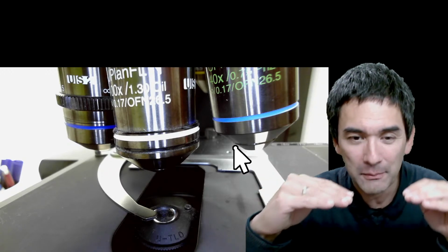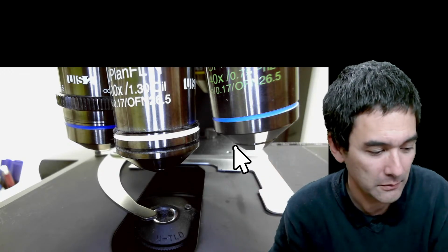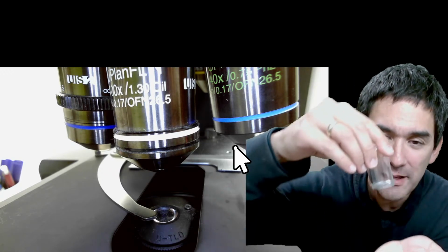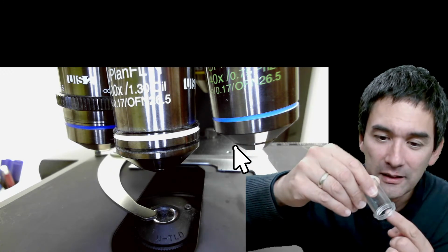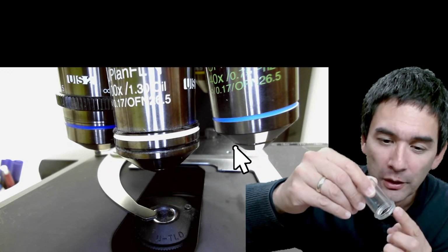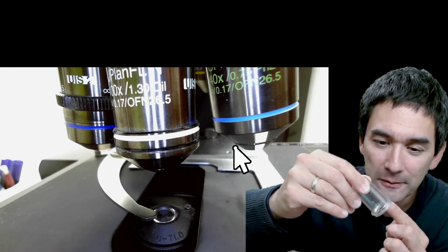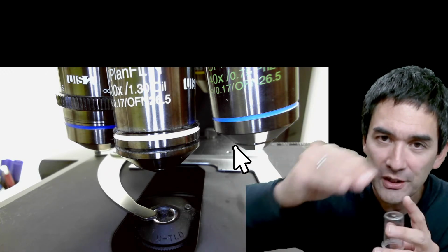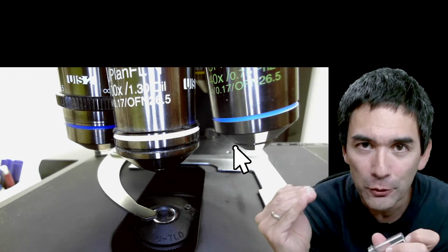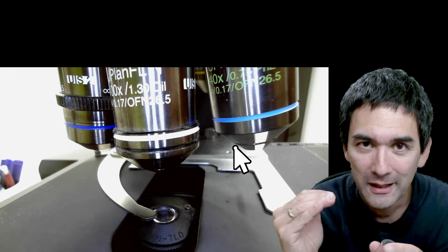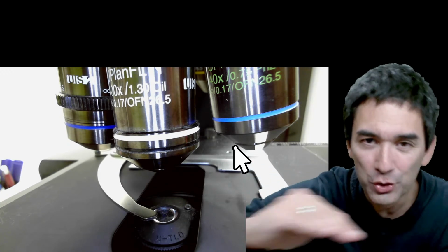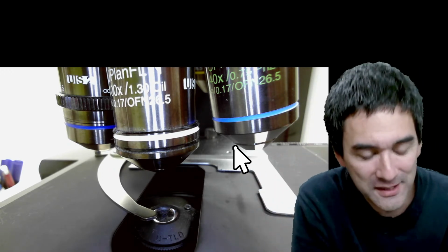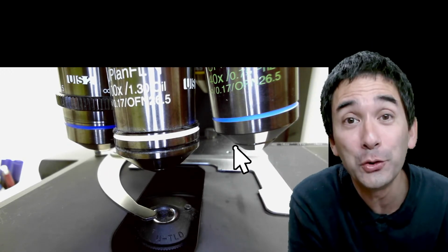Don't move it horizontally, but it's going to first, I'll use this here as an exaggerated analogy. Basically if you crash it in, then the lens is further inwards, and therefore it's first going to crash here on the side. And because the front lens is concave and goes inwards, it's sometimes difficult to clean. The dirt is in there, and if you just wipe over it superficially, you're not going to catch the dirt that's inside.